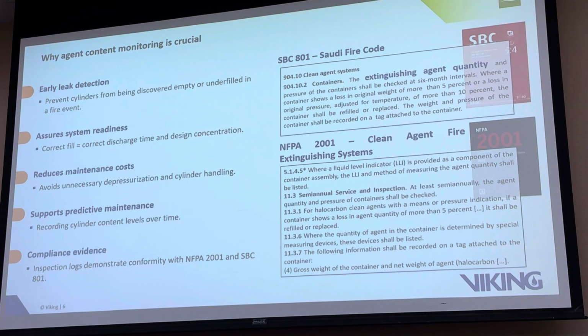So why is it crucial? Number one, early leak detection, right? If I measure the content and I see that today this is the amount of agent, I come over 1 month and I see, it seems like there's 100 grams less. And I go over time, it seems like there's 100 less grams, right? I predict that it seems like there's a leakage going on. So you can predict that earlier, whereas with a contact pressure gauge, you can only read the pressure, but you cannot acknowledge, right? Second is because it assures system readiness.